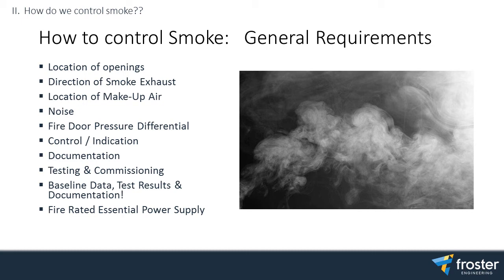Control indications. Baseline data. The consultant's documented, he's worked out you need 10,000 liters a second. That's your baseline design data that's been provided by the fire engineer. We want to see that at the commissioning test phase. So this is something that needs to be recorded and witnessed by both of us.